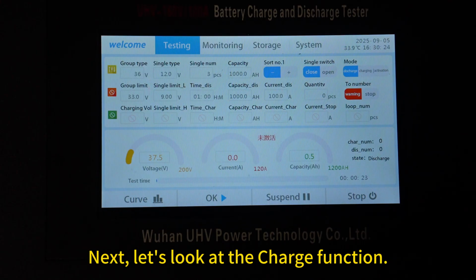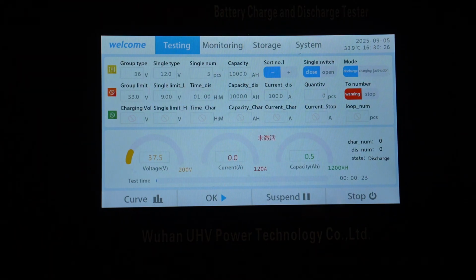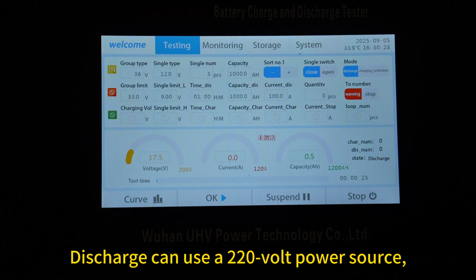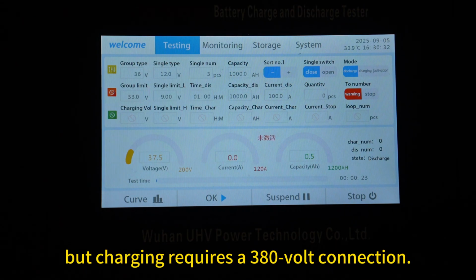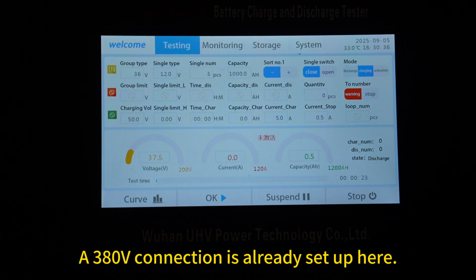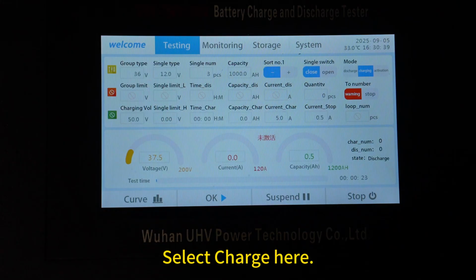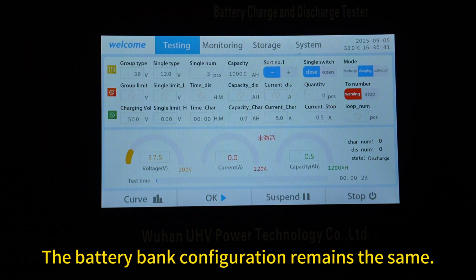Next, let's look at the charge function. Please note, discharge can use a 220-volt power source, but charging requires a 380-volt connection. A 380V connection is already set up here. Select Charge here. The battery bank configuration remains the same.